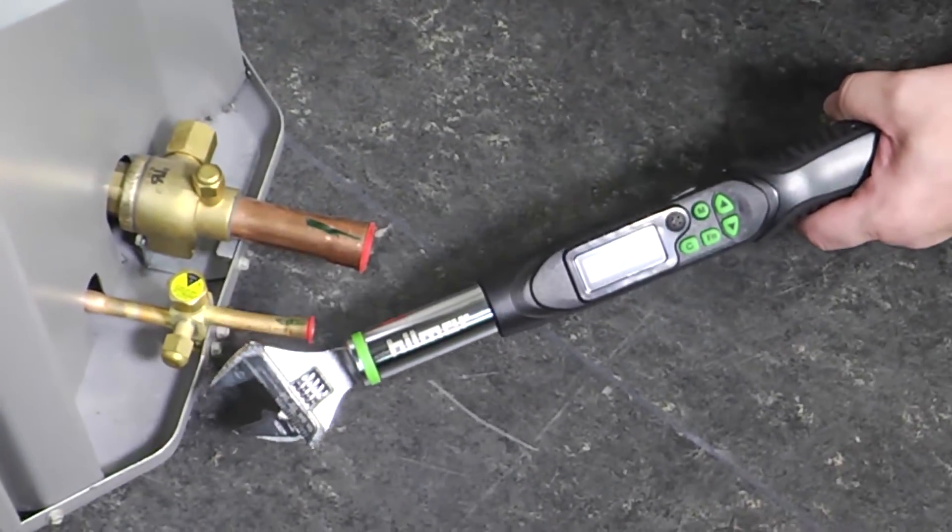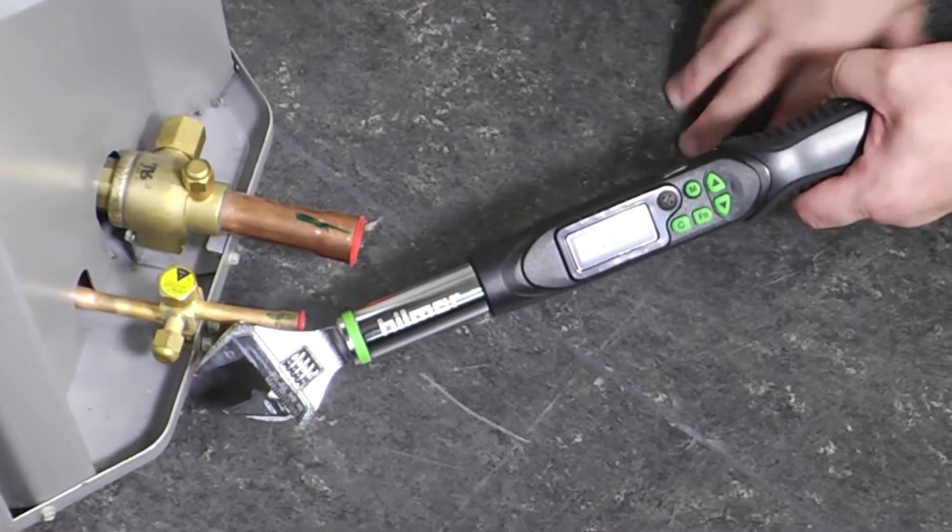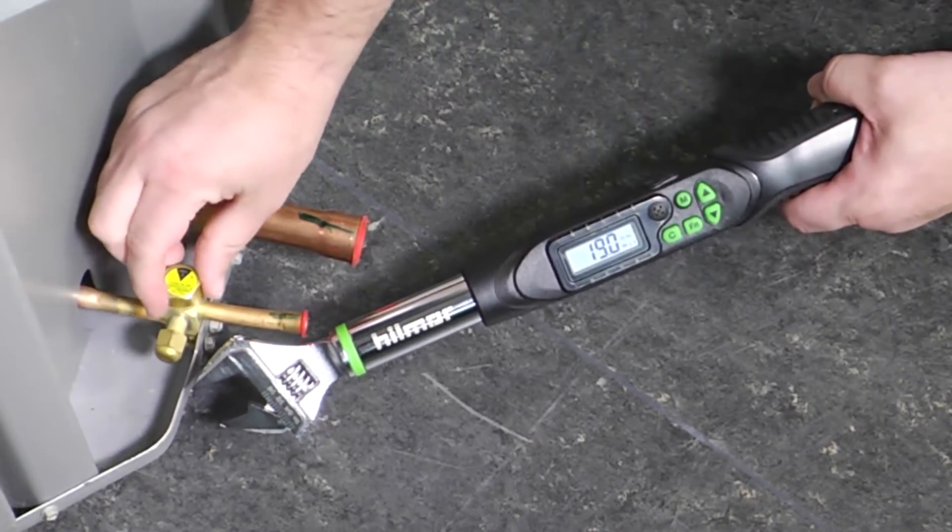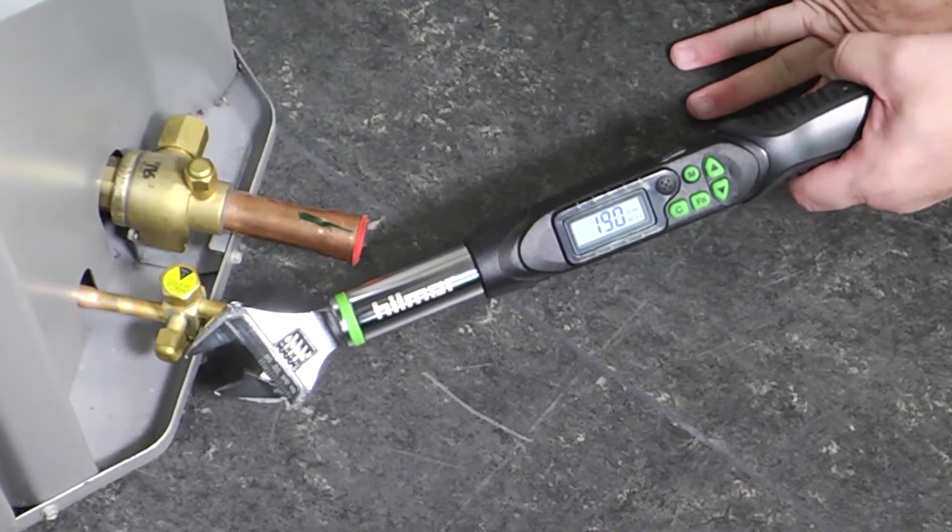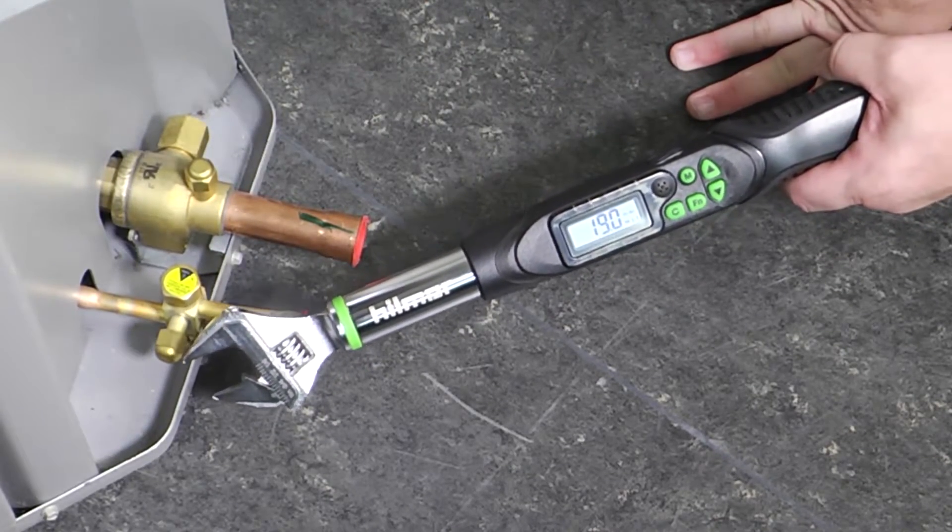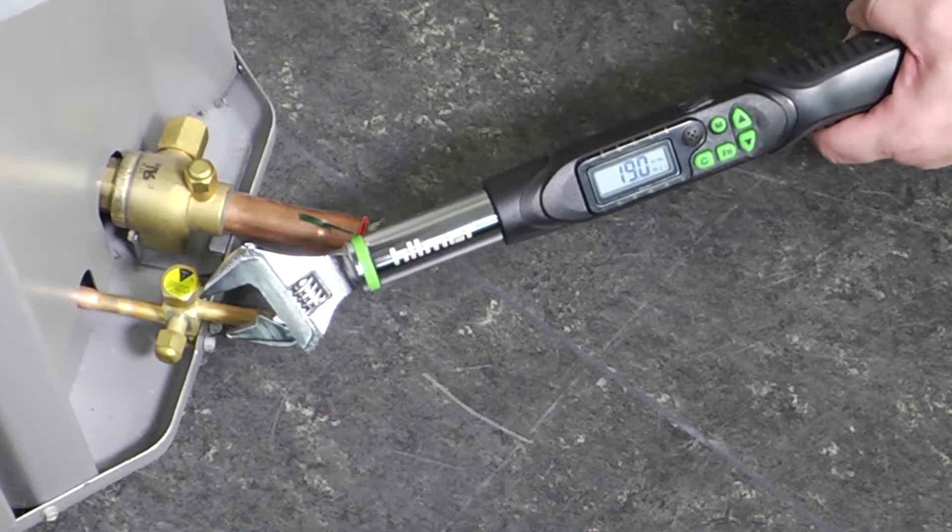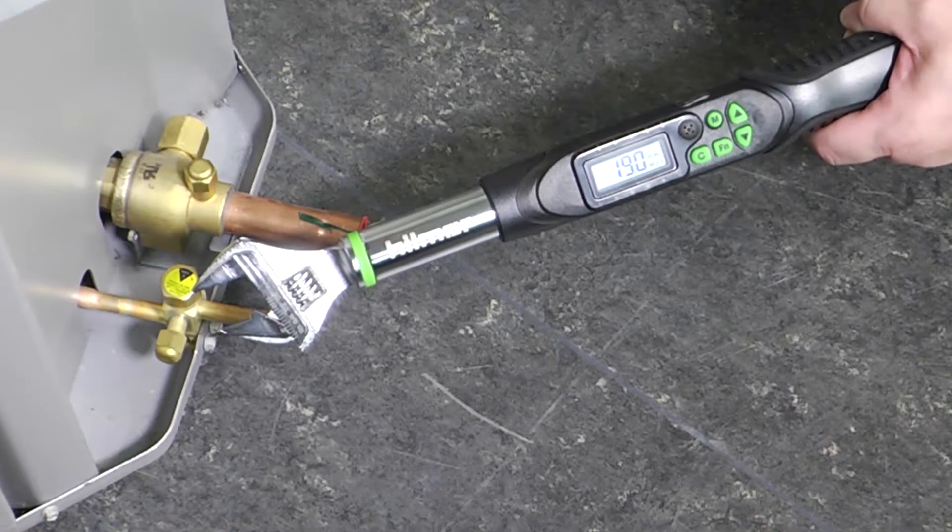Okay, so for this example here, we're looking at a service valve cap. Now normal rule of thumb is we would tighten them down finger tight and give it like a half a turn, a quarter turn, something like that. But if we wanted to be specific, a matter of fact, the installation manual for this unit says it should be tightened down to eight foot pounds.